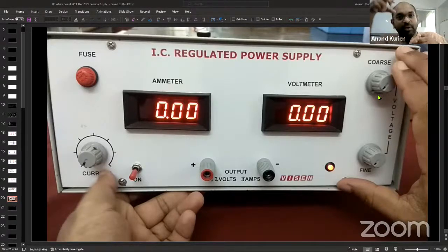Take the next voltmeter, put the two jacks in. What is the reading? Write it down, remove it, keep it away. Take the next one, put it in. What's the reading? Like this you do for 10 or 15. And then you will see some voltmeters will show you 2.2. Then you know that you can't use that. Are you with me? Some will show you 3.5 or 3, well beyond 3. Then you can't use that.